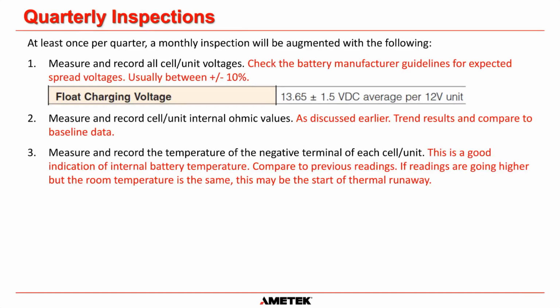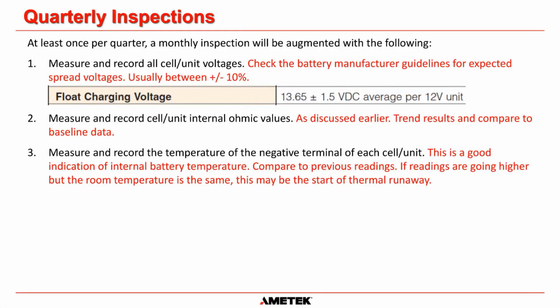So once again, you can see on the screen here this box. Oh, goodness me, my circle is terrible. But that box there is actually from a C&D battery. I think it was the same battery that we looked at before that had the baseline resistance in it. And it says for float charge voltage, it should be at 13.65 volts. So this is a 6-cell jar, and the spread should be plus or minus 1.5 volts DC.